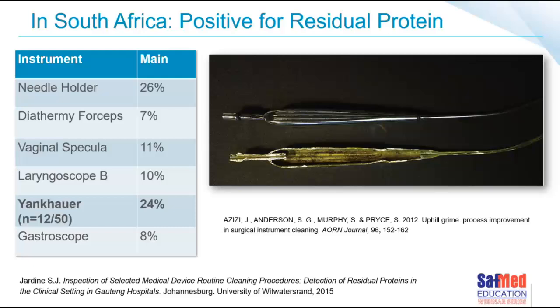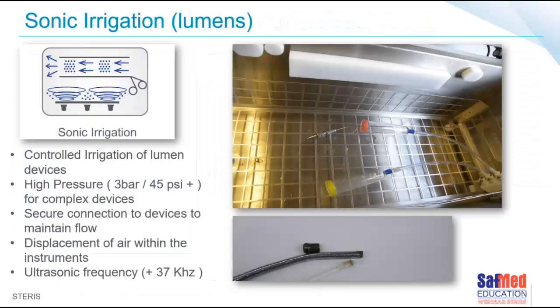But either way, a brush that'll fit through the lumen of the tip or fit through the lumen at the back end of the sucker is not going to be big enough to clean inside that big bulb section. And you can see over there how dirty that bulb is. Now, that's a device that's really only going to come clean properly if you use an ultrasonic lumen flush scenario. So let's have a look at ultrasonic lumen flush.